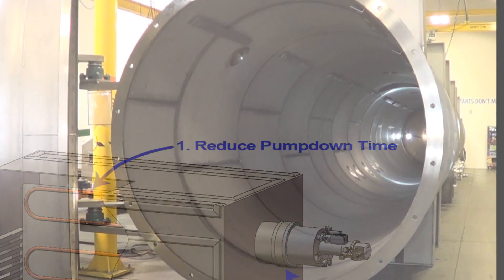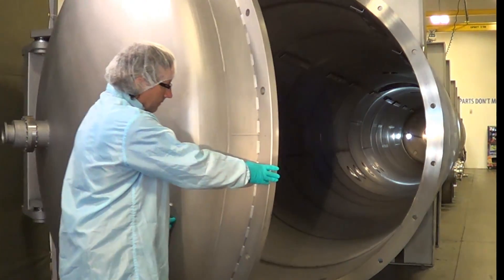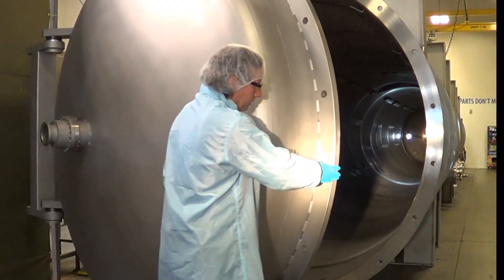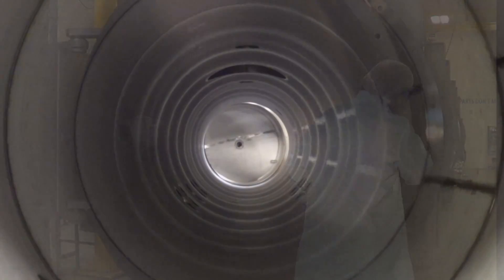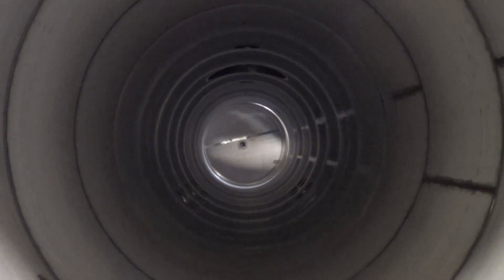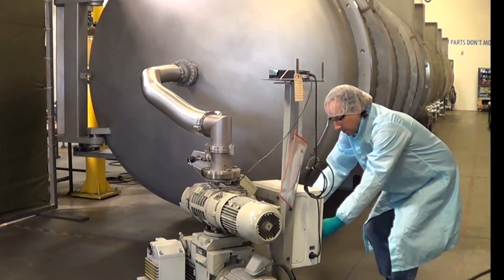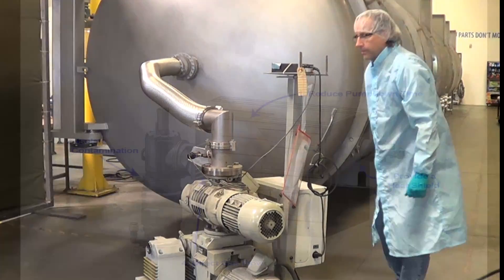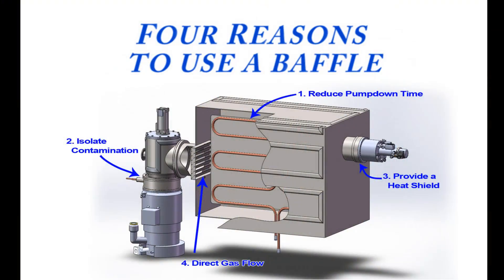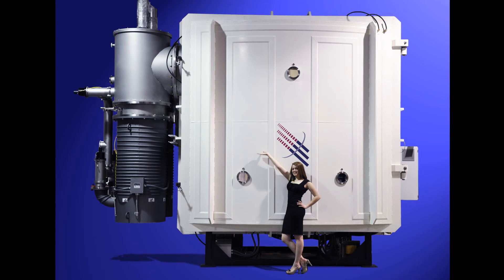For most systems, water vapor comprises between sixty to ninety-five percent of the residual gas load. By creating a cold surface, the partial pressure of water vapor is lowered, thus significantly reducing the required pumping capacity and reducing evacuation time.